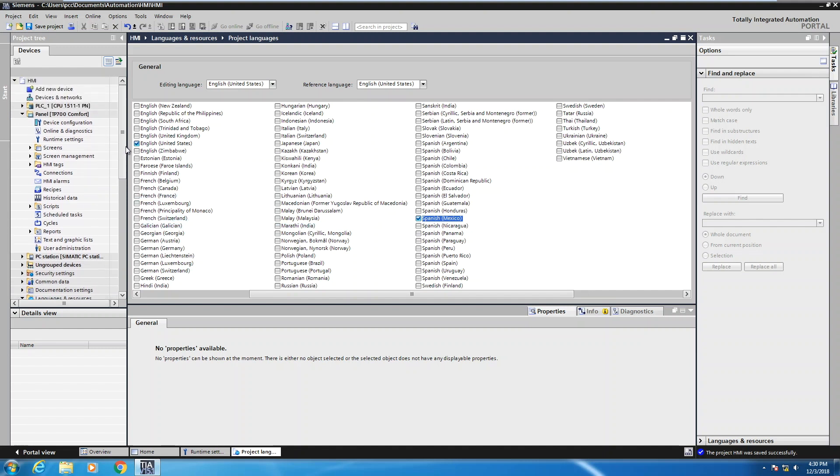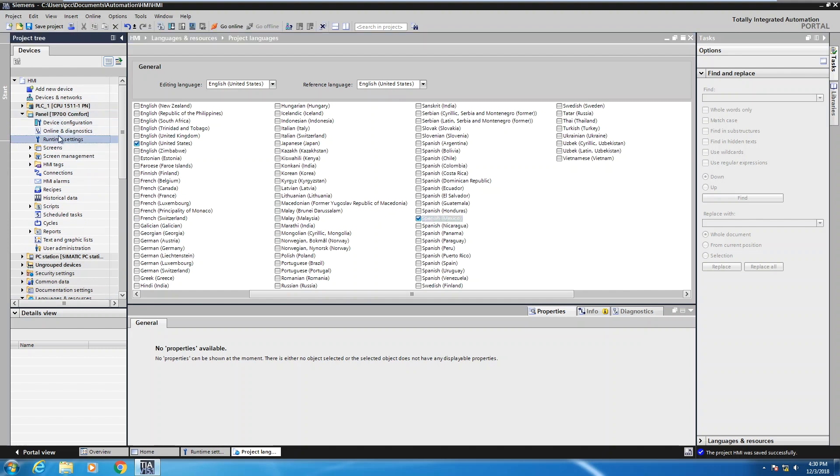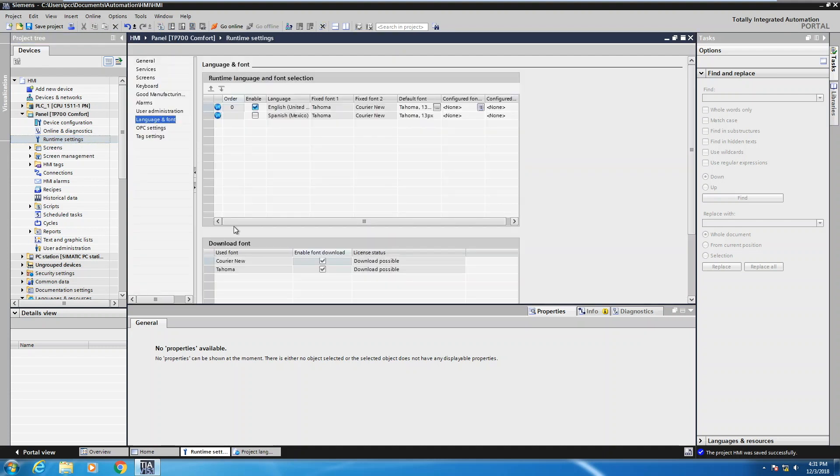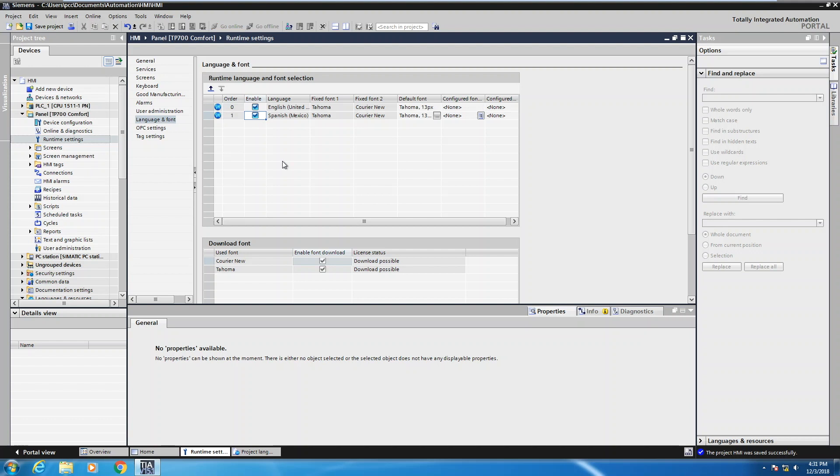Once I add the language into the application, the next thing I need to do is go up by my panel and then look for the runtime settings and double click on runtime settings. Then for the runtime language and font, you will have to enable the language that you just added because it's possible to add many languages in your application, but unless you enable it here, it's not going to be downloaded to the panel.